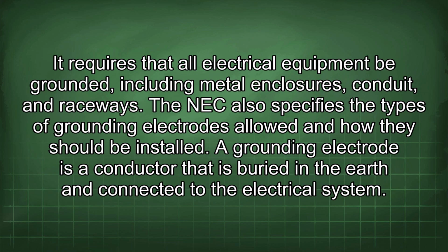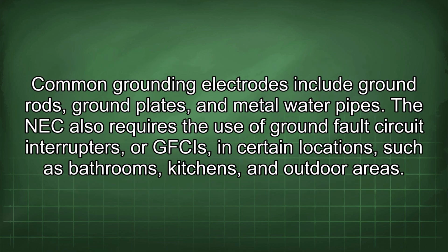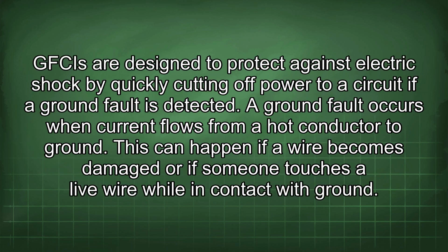It requires that all electrical equipment be grounded, including metal enclosures, conduit, and raceways. The NEC also specifies the types of grounding electrodes allowed and how they should be installed. A grounding electrode is a conductor that is buried in the earth and connected to the electrical system. Common grounding electrodes include ground rods, ground plates, and metal water pipes. The NEC also requires the use of ground fault circuit interrupters, or GFCIs, in certain locations such as bathrooms, kitchens, and outdoor areas. GFCIs are designed to protect against electric shock by quickly cutting off power to a circuit if a ground fault is detected.